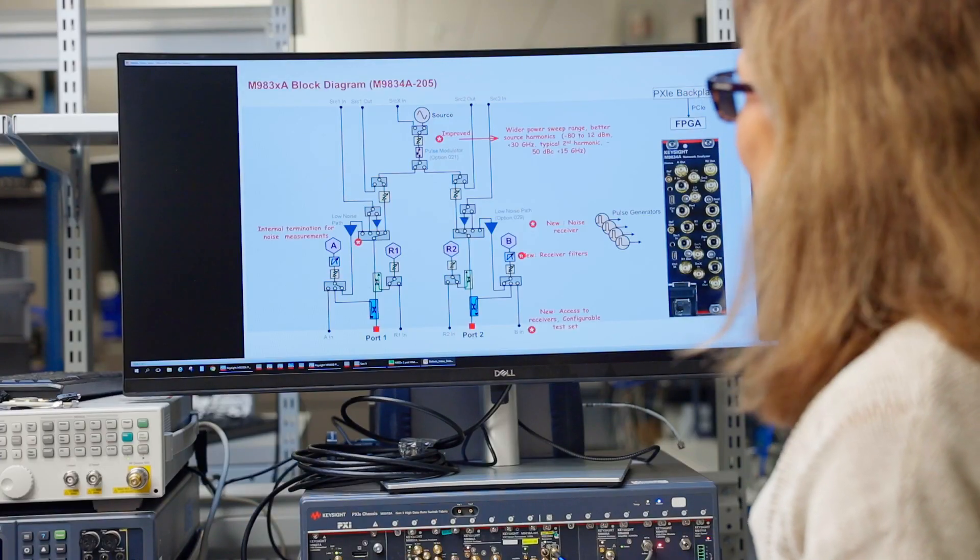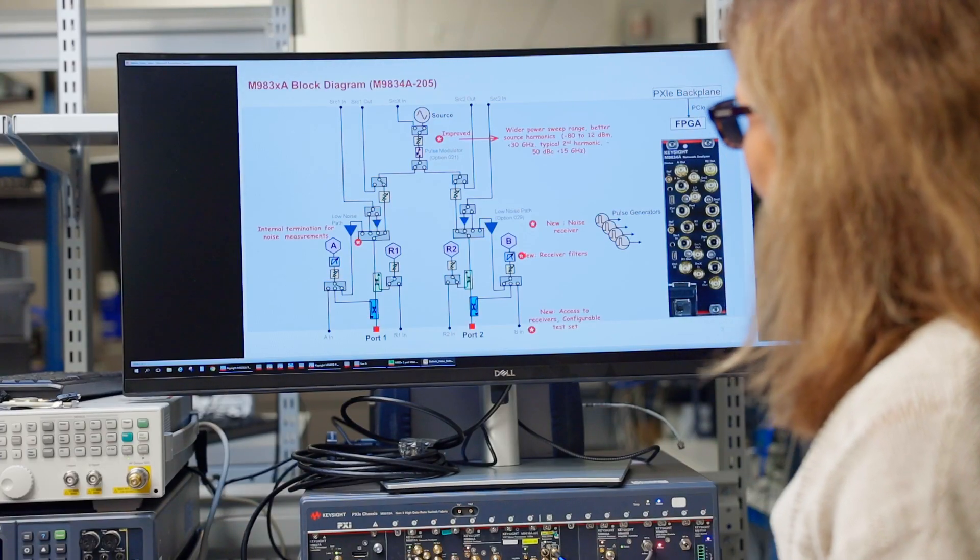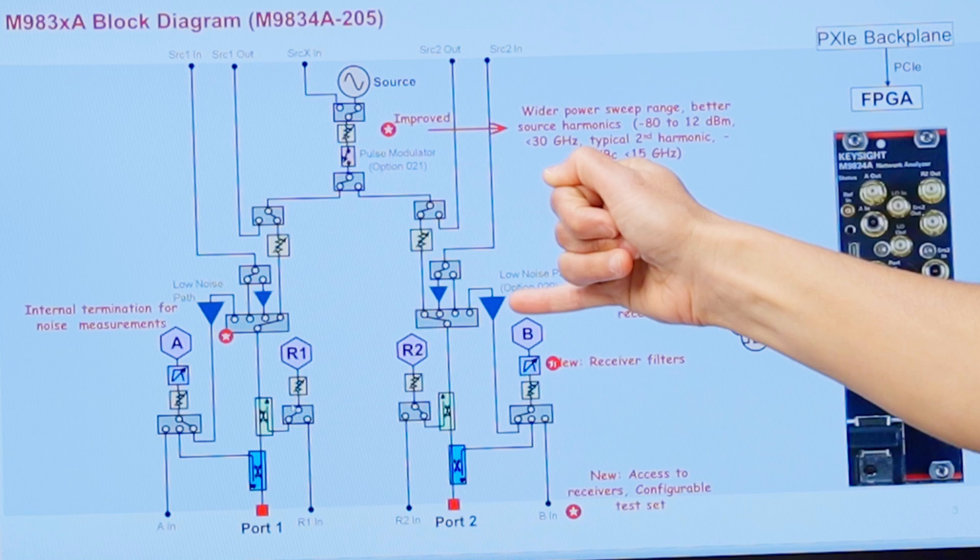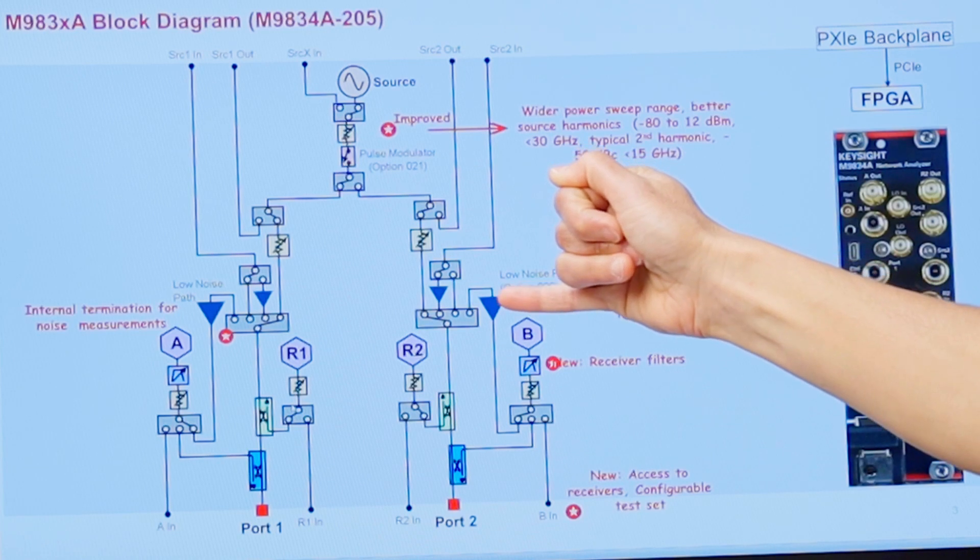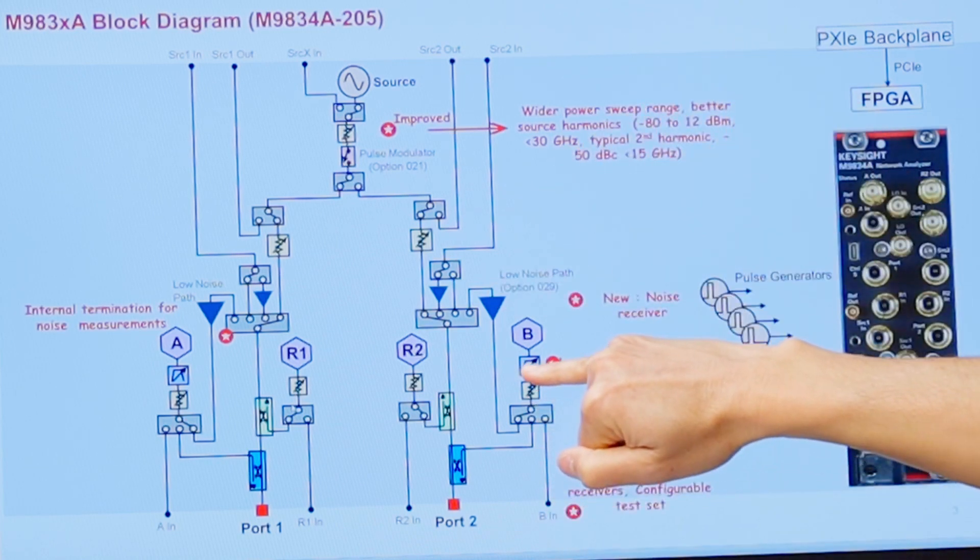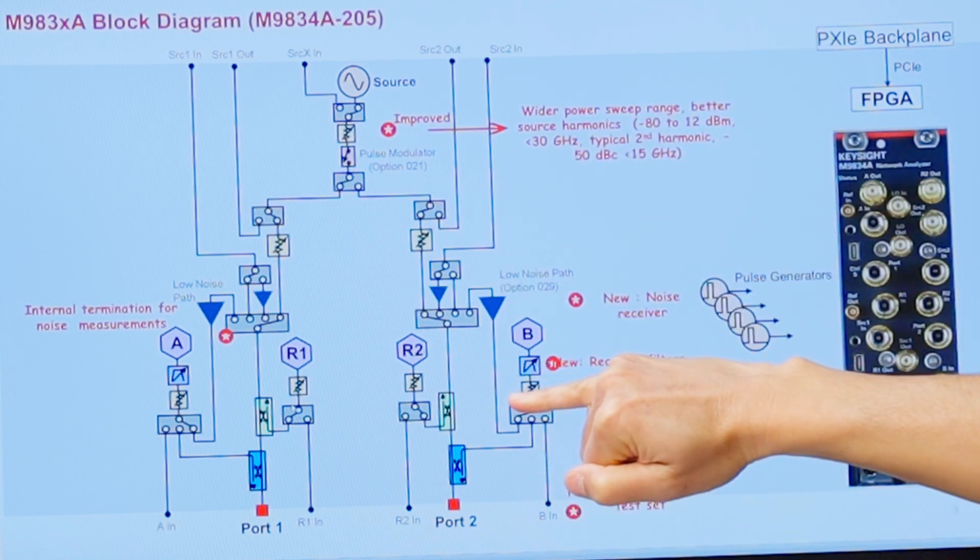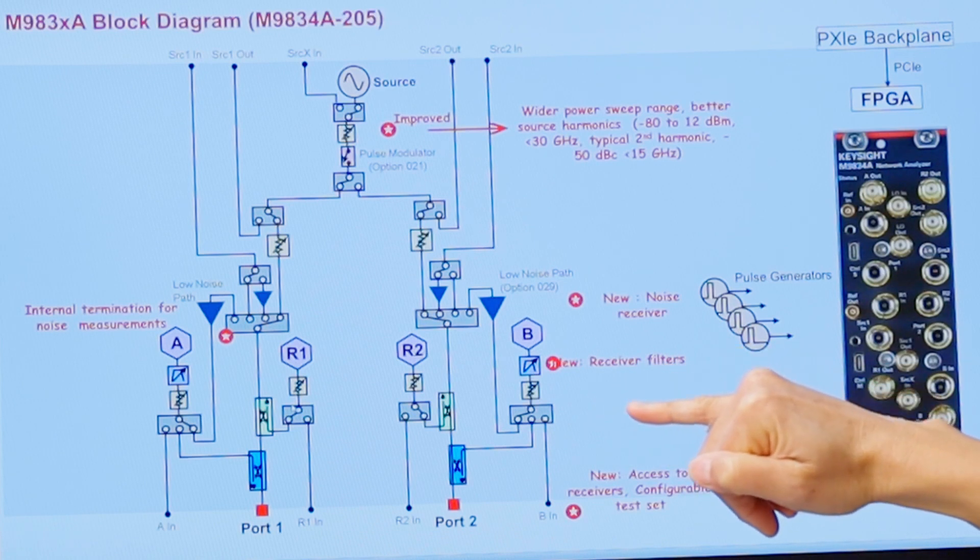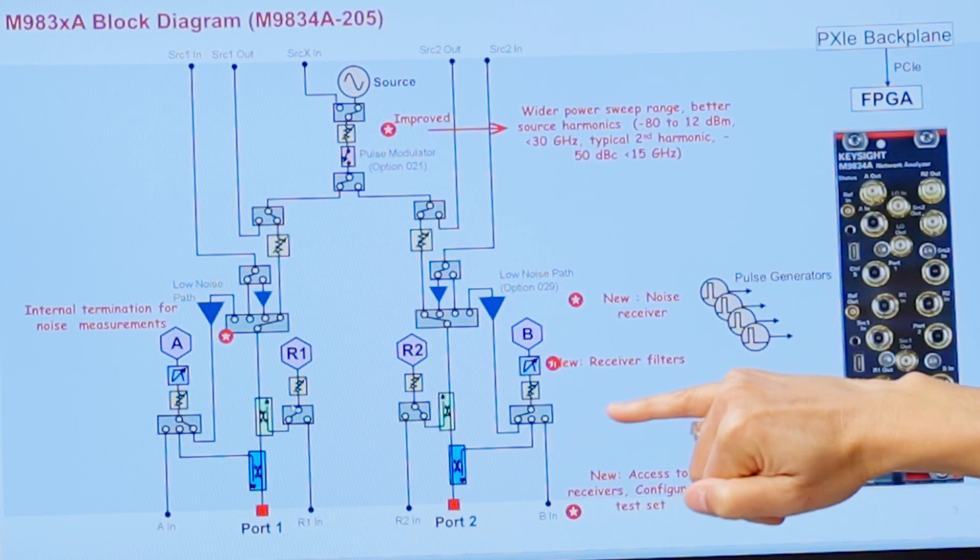So let's take a quick look at the hardware block diagram. Here you can see the LNAs in the path that are used for the noise figure measurement. I wanted to point out there's also filters in the receiver path. These can be beneficial in harmonic distortion measurements for example, to tune out the fundamental from reaching the receiver.